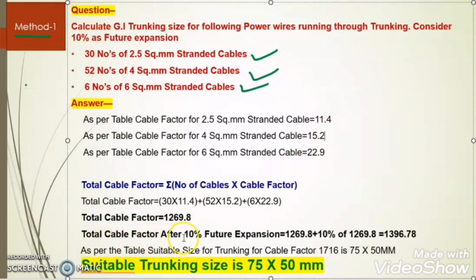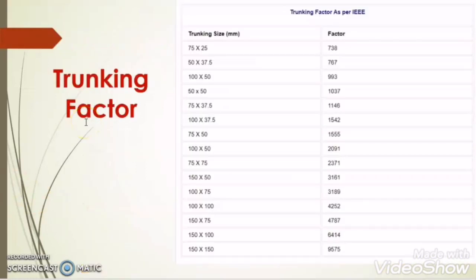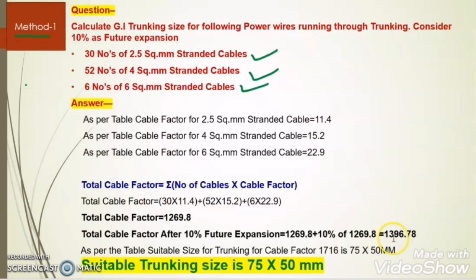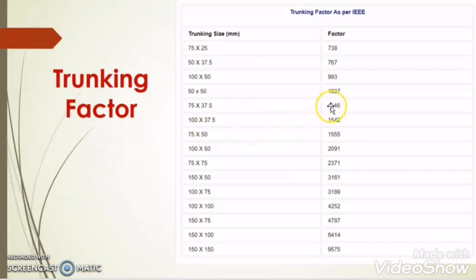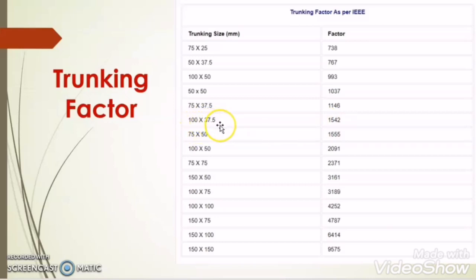As per the question, we have to take 10% as future expansion, so we add 10% to this value. After calculating, the total cable factor is 1396.78. This factor we have to compare with the trunking factor and select the trunking factor which is greater than our calculated factor. The next value is 1542, so we can select the trunking size as 100 x 37.5.